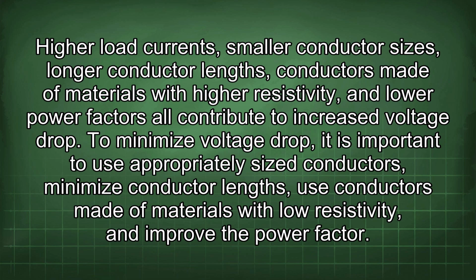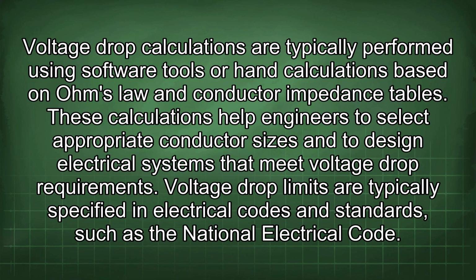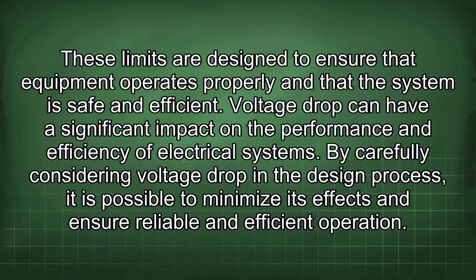To minimize voltage drop, it is important to use appropriately sized conductors, minimize conductor lengths, use conductors made of materials with low resistivity, and improve the power factor. Voltage drop calculations are typically performed using software tools or hand calculations based on Ohm's law and conductor impedance tables. These calculations help engineers to select appropriate conductor sizes and to design electrical systems that meet voltage drop requirements. Voltage drop limits are typically specified in electrical codes and standards, such as the National Electrical Code. These limits are designed to ensure that equipment operates properly and that the system is safe and efficient. Voltage drop can have a significant impact on the performance and efficiency of electrical systems. By carefully considering voltage drop in the design process, it is possible to minimize its effects and ensure reliable and efficient operation.